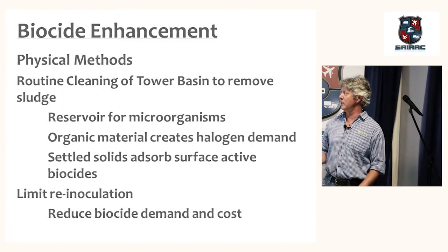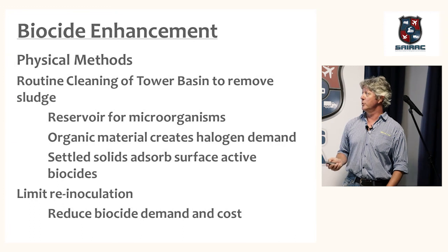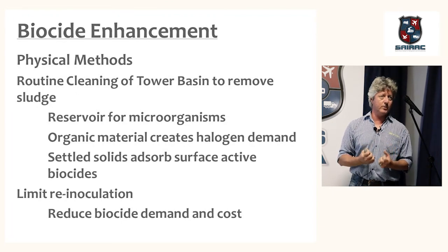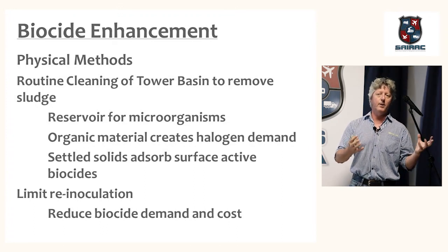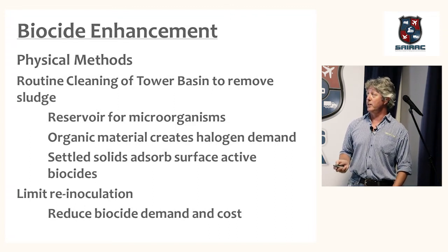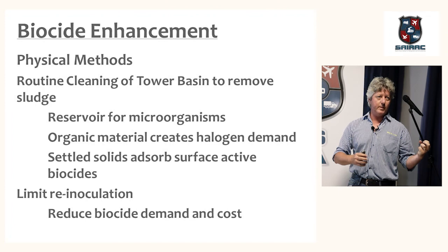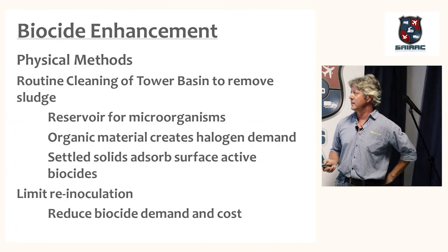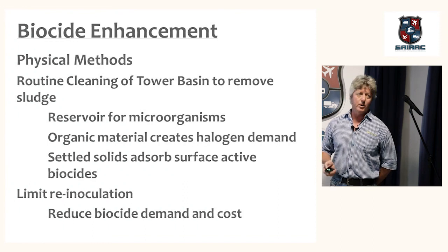Organic material creates a huge halogen demand, but we're staying away from halogens as far as we can. Settled solids absorb surface active biocides. So the solids can actually absorb some of the biocides that we add to kill the bacteria. So the solids can reduce the effectiveness of your biocide. Limit re-inoculation. So in other words, if you have solids floating around, it can be covered in bacteria. Part of it might be killed, another part might not, so it re-inoculates your system continuously. And if you have all these things in place, you will reduce your biocide demand and you will reduce your cost.